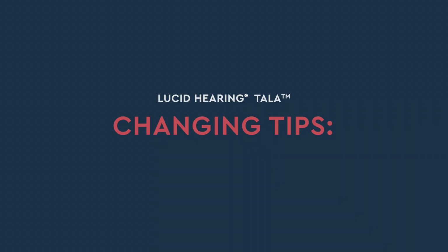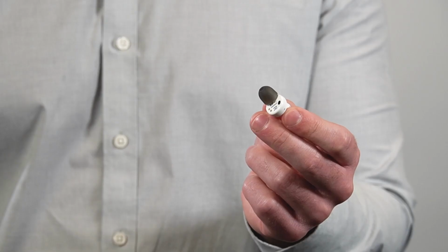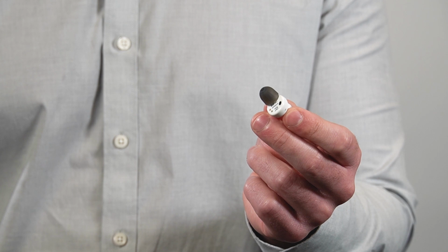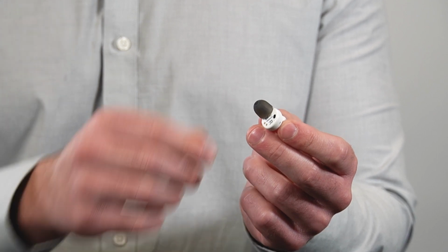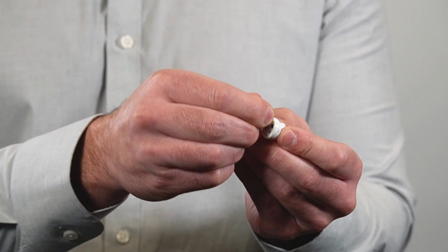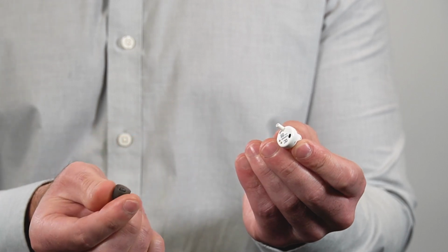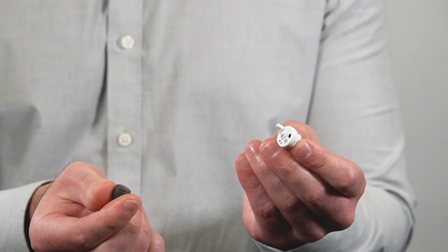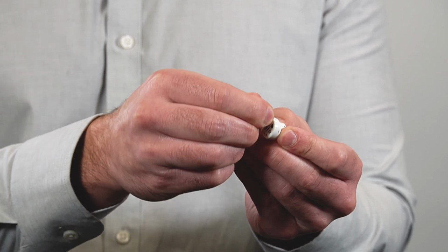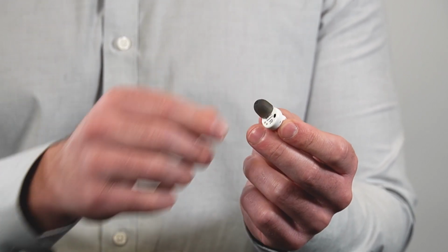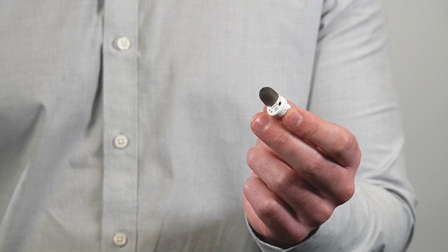Changing tips. To change your ear tip, begin by holding the Tala by its stem. Gently pull on the tip until it comes off. You may need to twist it using a back and forth motion. Next, align the new tip with the dome facing outward and press the new tip on until tip is nearly flush with the device. Make sure to secure the tip well.